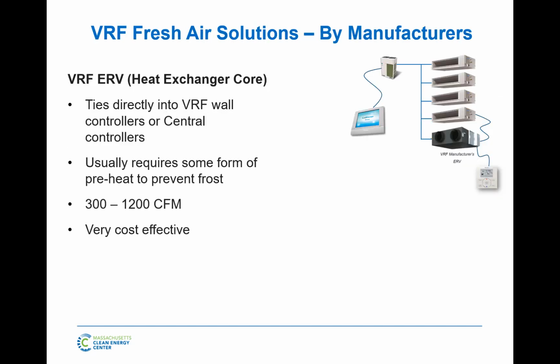A lot of manufacturers have a VRF ERV. We're going to get good at acronyms here today. It's a mouthful. But these are ERVs, or energy recovery ventilators, built by the VRF manufacturers. This is what it looks like over here. It's a box with a couple of fans and the core in the middle, like I mentioned earlier, a little rectangular core. The pros and cons of these: what's great about them is they're very simple, very cost effective, and pretty small, and you can put them up in a ceiling pretty easily. Control-wise, they can integrate right in with the VRF controls. They can interlock with other fan coils easily or with central controllers. We'll talk about that later.